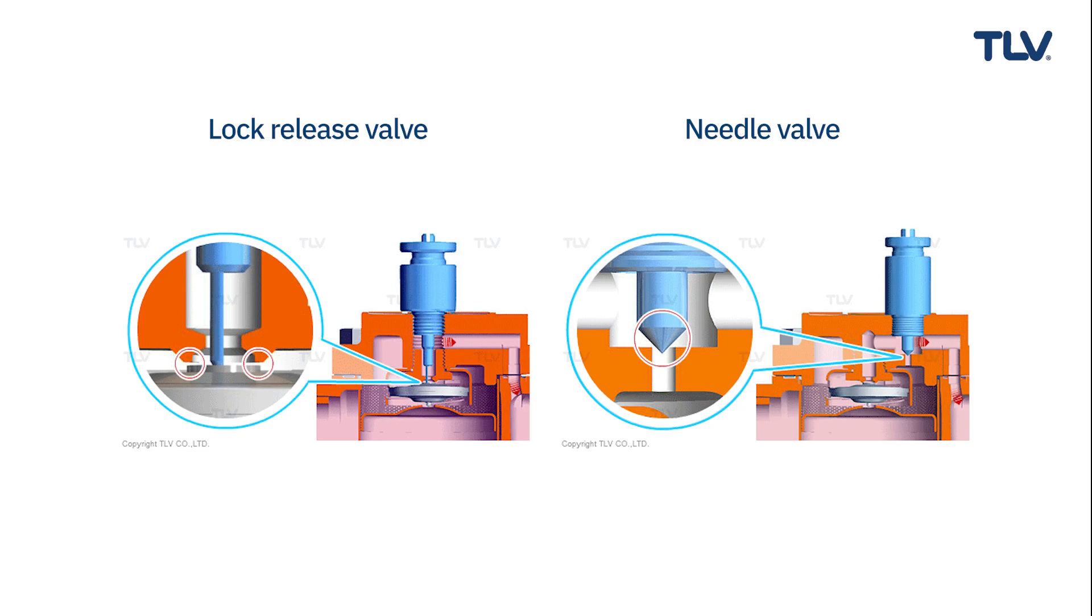Another countermeasure is the use of a lock release valve or needle valve to allow steam to be released to the downstream side of the trap, fixing the steam locking problem. Since lock release valves and needle valves can control the release of steam, steam loss is minimized.